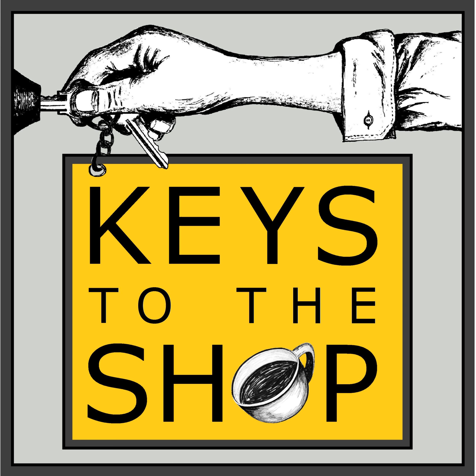Let me talk briefly about probably the biggest maintenance issue I see on these undercounter units and any reach-in equipment. Probably the biggest failure is the unit runs warm, and I get there, pull the unit out, and there's a sweater, as I like to call it, over the condenser.